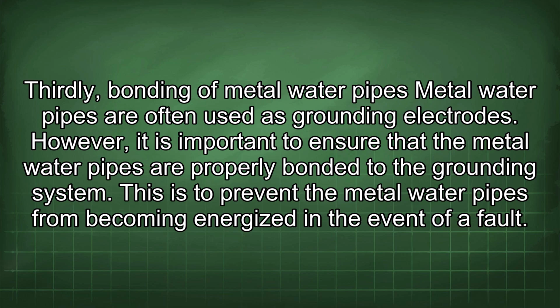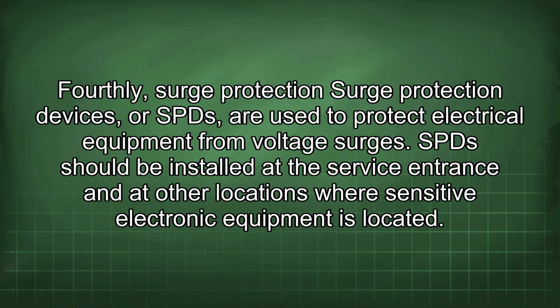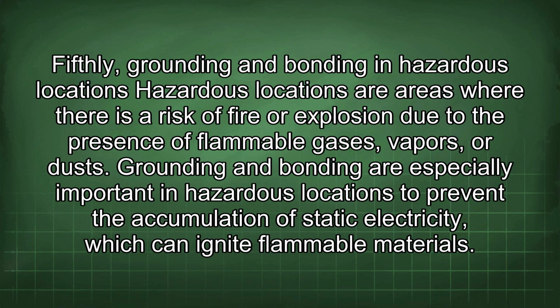Thirdly, bonding of metal water pipes. Metal water pipes are often used as grounding electrodes. However, it is important to ensure that the metal water pipes are properly bonded to the grounding system. This is to prevent the metal water pipes from becoming energized in the event of a fault. Fourthly, surge protection. Surge protection devices, or SPDs, are used to protect electrical equipment from voltage surges. SPDs should be installed at the service entrance and other locations where sensitive electronic equipment is located. Fifthly, grounding and bonding in hazardous locations. Hazardous locations are areas where there is a risk of fire or explosion due to the presence of flammable gases, vapors, or dusts. Grounding and bonding are especially important in hazardous locations to prevent the accumulation of static electricity which can ignite flammable materials.